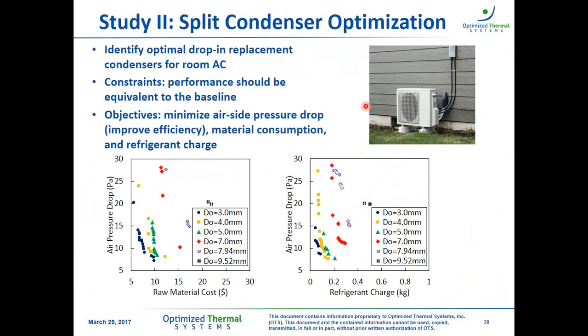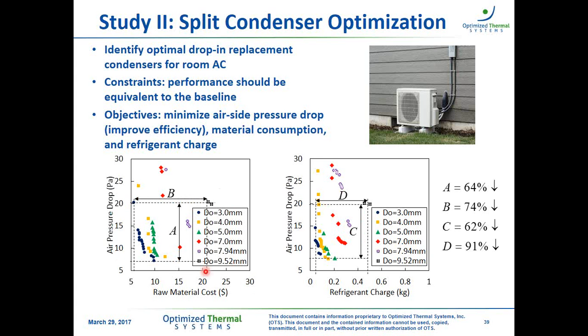The second study is a split condenser optimization, as I said before, targeting minimizing the air side pressure drop and the raw material cost. So we have actually 2 sets of optimizations, and the other one is air side pressure drop and refrigerant charge. And these are all the Pareto fronts for each tube diameter size, from 3 all the way to 9.5. So the 3 is here, the 9.5 is over here. What is interesting to see is the potential improvement that we get out of this. From this study, what we're showing is that from both optimizations, the maximum pressure drop reduction we got is around 60% if we compare 9.5 with a 3 millimeter, or even a 4 or 5 millimeter.